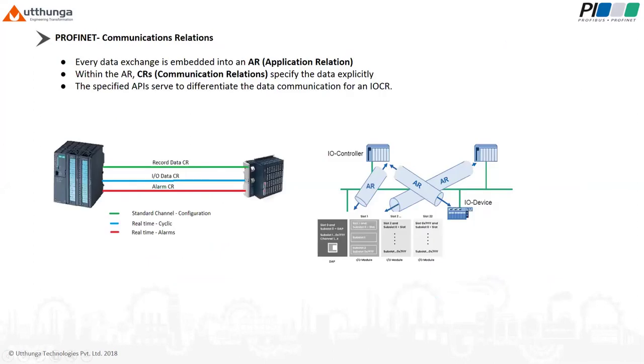Communication relations. To establish communication between the higher level controller and an IO device, communication paths must be established. Every data exchange will be embedded into application relations. Within the application relations are the communication relations, which specify the data explicitly. As a result, all data for the device modeling, including the general communication parameters, are downloaded to the IO device.